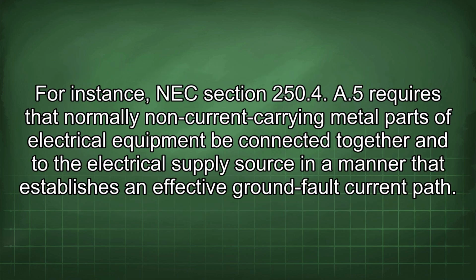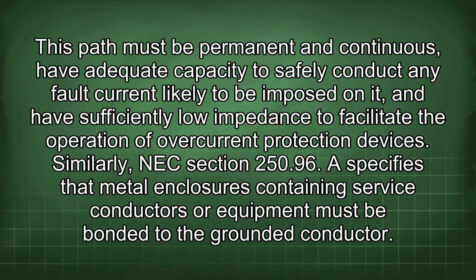For instance, NEC Section 250.4(A)(5) requires that normally non-current carrying metal parts of electrical equipment be connected together to the electrical supply source in a manner that establishes an effective ground fault current path. This path must be permanent and continuous, have adequate capacity to safely conduct any fault current likely to be imposed on it, and have sufficiently low impedance to facilitate the operation of overcurrent protection devices.